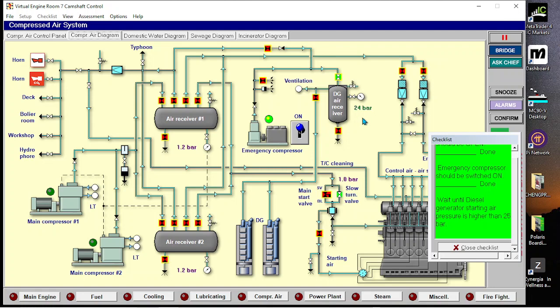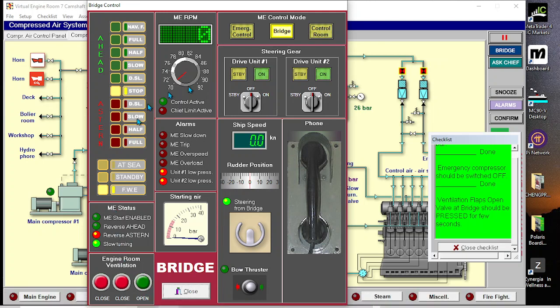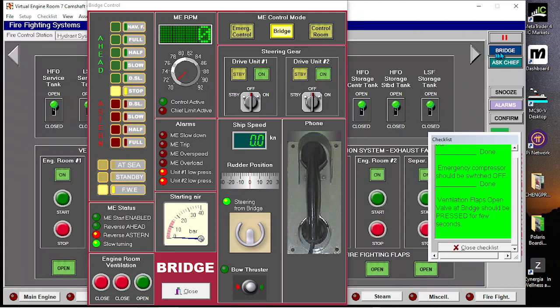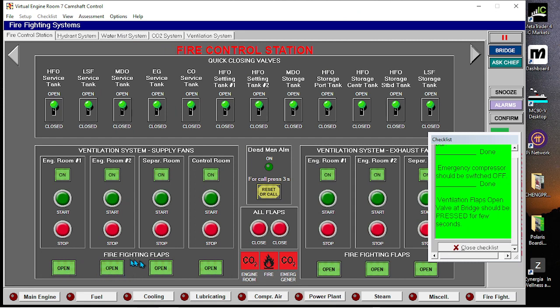23. Emergency compressor should be switched off, so we are going to switch off this. Ventilation flaps open valve at bridge should be pressed for a few seconds. We are going to open these ventilation flaps, and these flaps are in the firefighting. As you can see, these firefighting flaps are closed. So flaps for engine room fan 1, engine room fan 2, separator room, and the control room. Before we open these supply fans, we need to open these flaps.